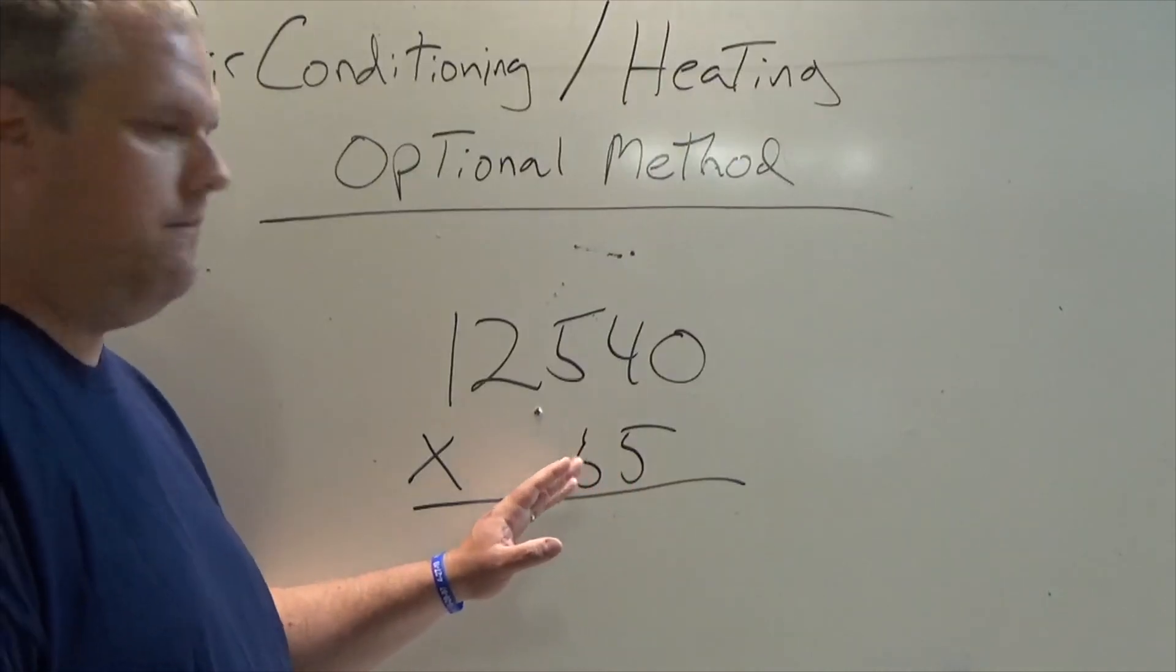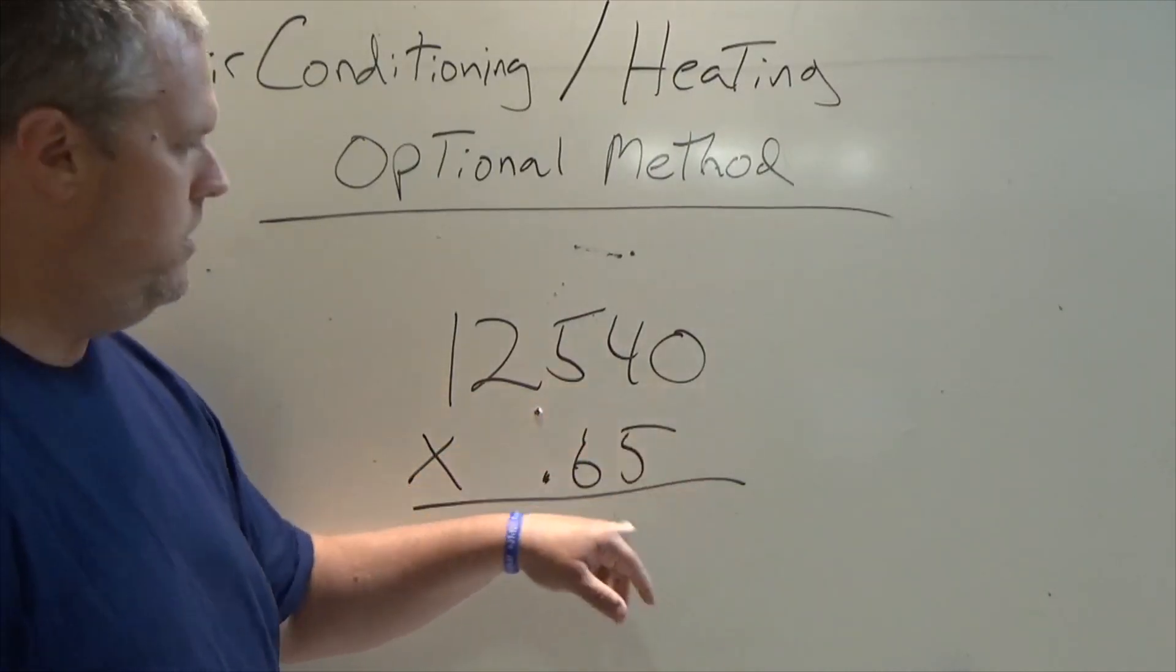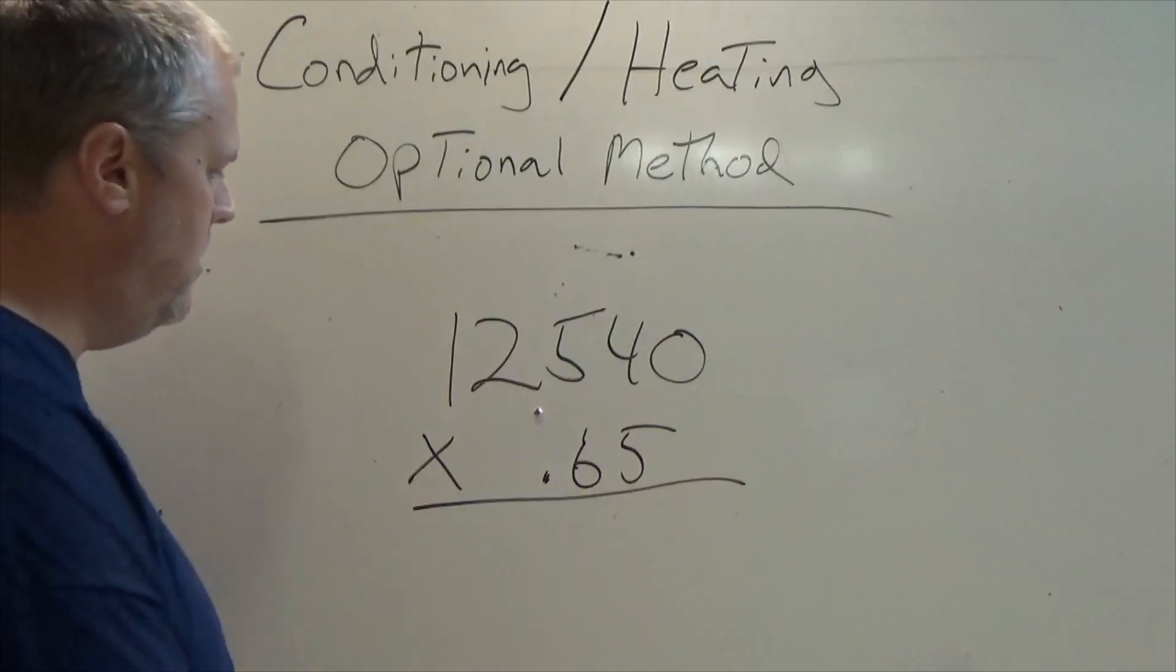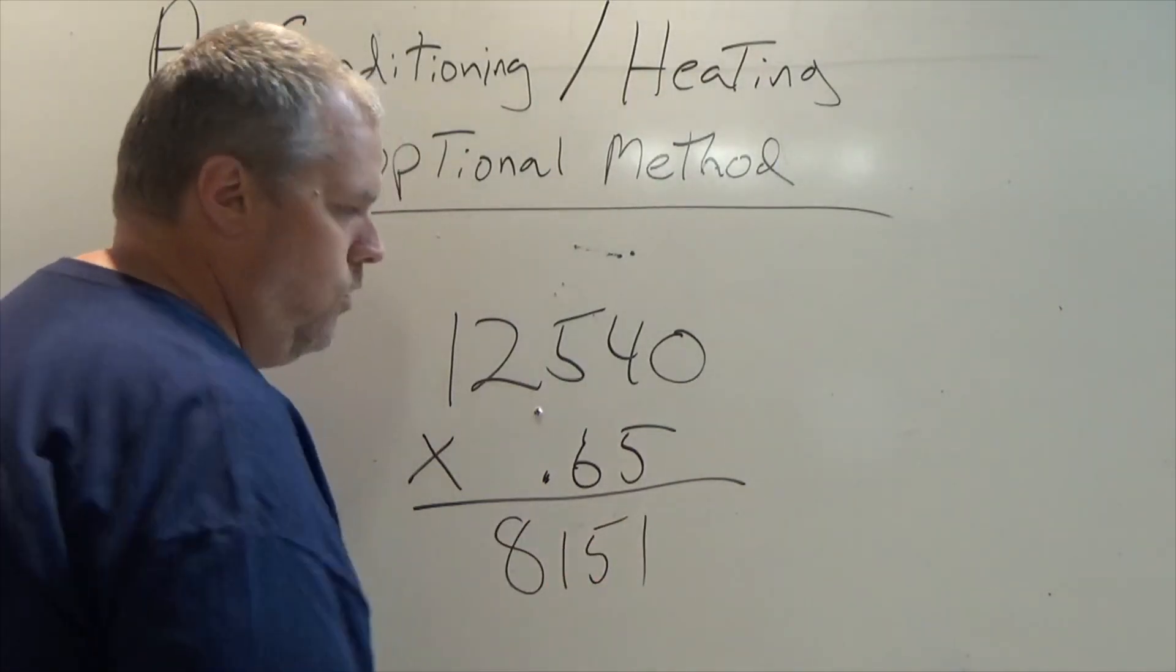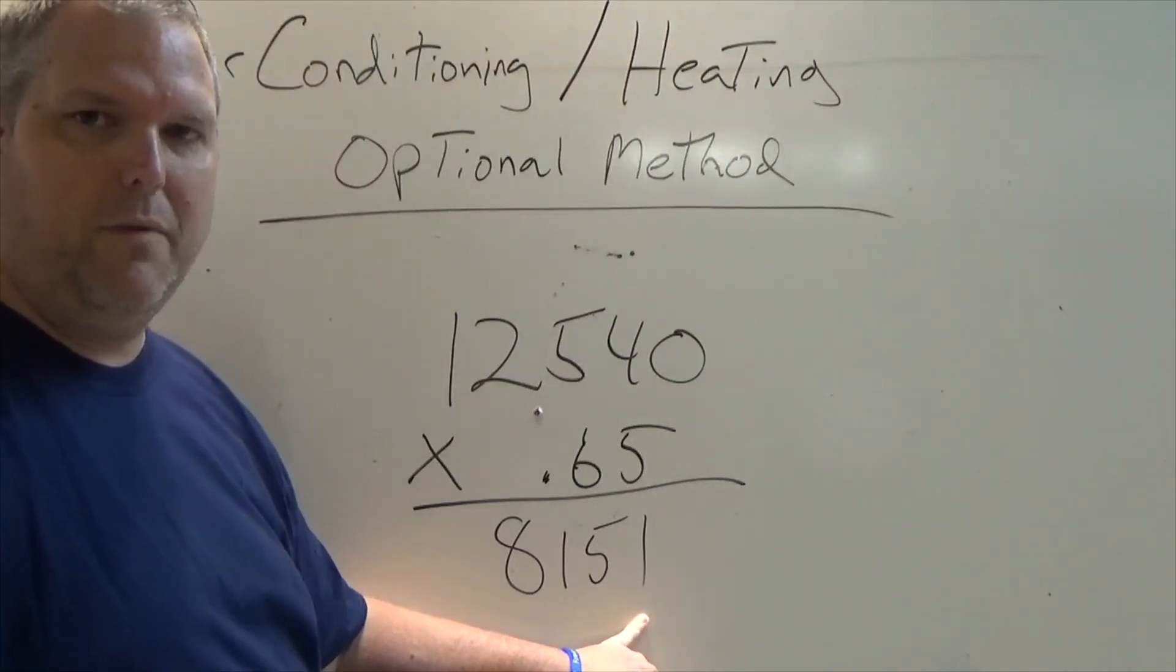Because there's three units, I'm going to multiply that by 65%. So now that I have this set up, I'm going to take the 12,540, multiply it by 65%, and it's going to give me 8151. This is my VA for my heating.